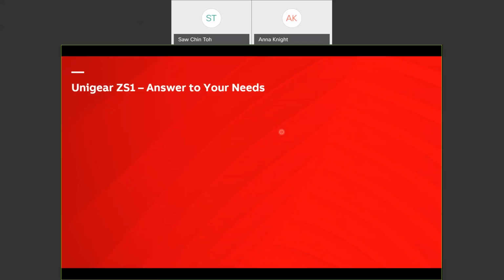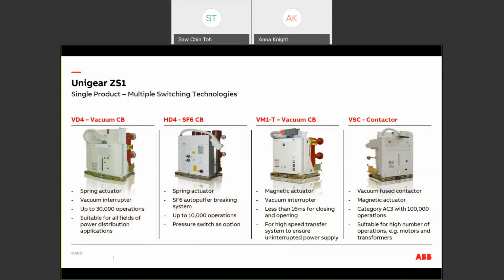We have developed many products over the years to suit different switching requirements, so we can put many types of apparatus into UniGear ZS1. The most commonly used is the VD4 vacuum circuit breaker. It has a spring actuator and is suitable for all types of power distribution applications. This is the most common type of circuit breaker, suitable to switch distribution lines, transformers, capacitors, and motors.